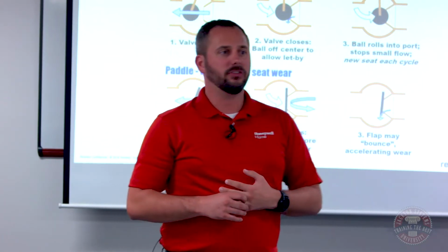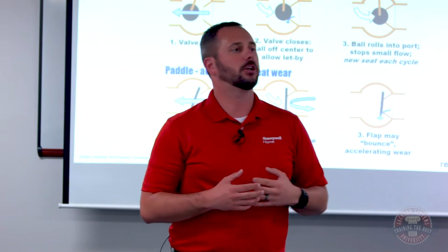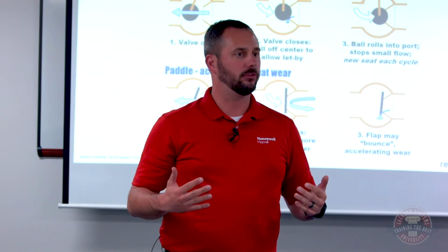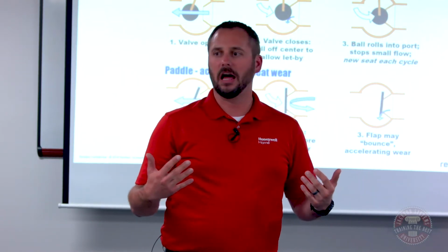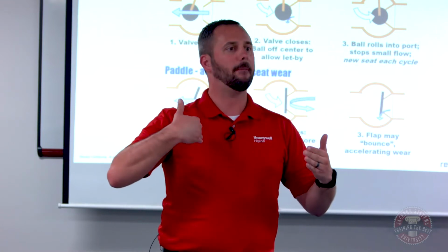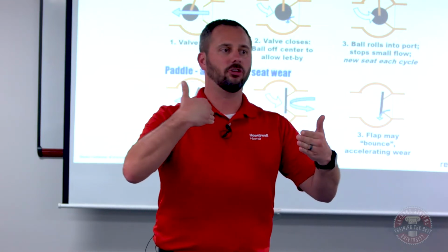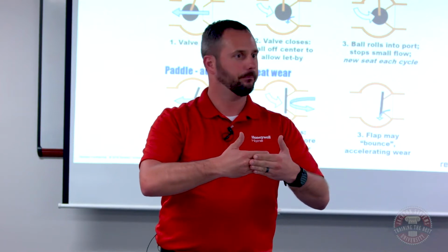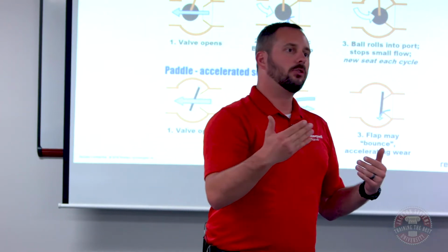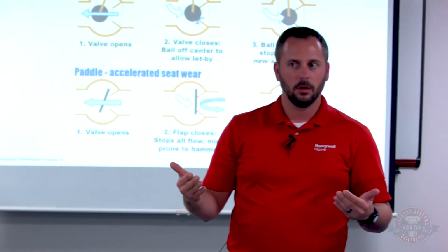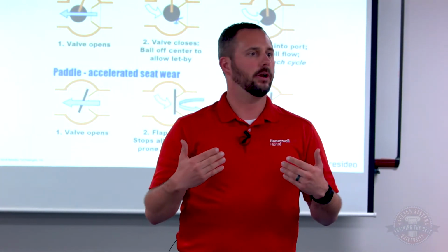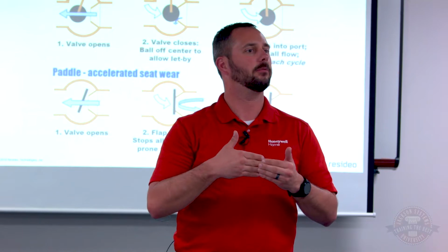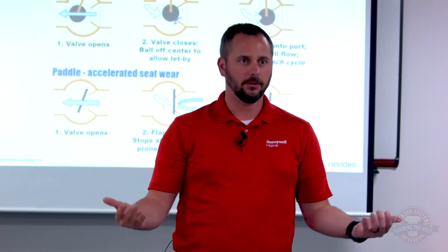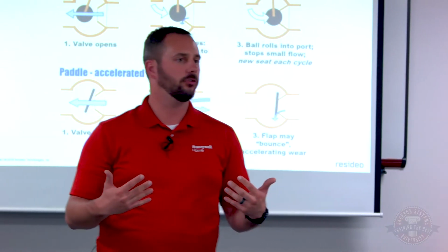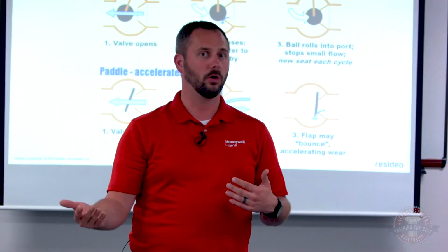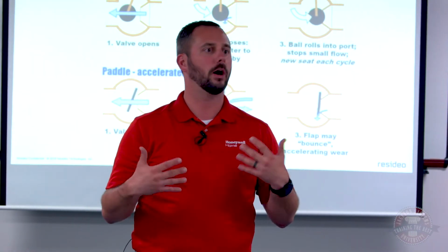What happens on a paddle series valve, and I'm not going to pick on any manufacturers, but there are several manufacturers that use a paddle series valve. The paddle is a lot like a toilet flapper. When that paddle shuts, it's shutting all the water off very hard, very fast. So it not only creates the potential for water hammer, but it also provides accelerated wear because it's always closing in the exact same spot every time. If the boiler water wasn't treated before it was installed, it'll accelerate it even more. Ours will get eaten up eventually if the boiler water is not treated.